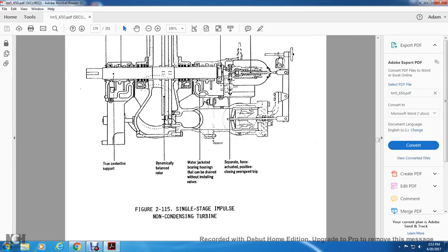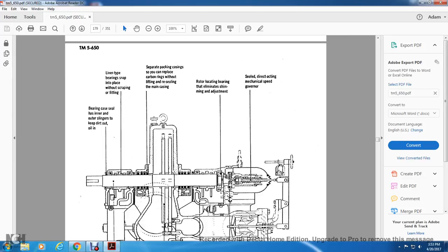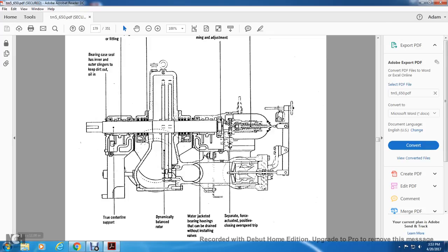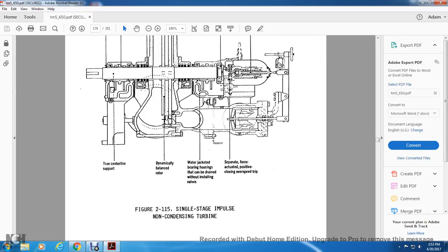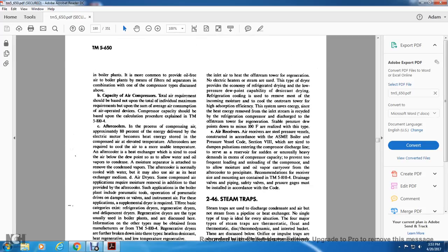This shows a single-stage impulse non-condensing turbine. The bearing case has inner and outer slingers keeping the dirt out. Liner bearings snap into place without scraping. A separate packing case lets you replace carbon rings without lifting the main case. Rotor locating bearing eliminates shimming and adjustment. Sealed, direct-acting mechanical speed governor. True centerline, dynamically balanced rotor, and a water jacket bearing housing that can be drained without isolation valves. A separate force-actuated positive closing overspeed trip. That's a single-stage impulse non-condensing turbine.